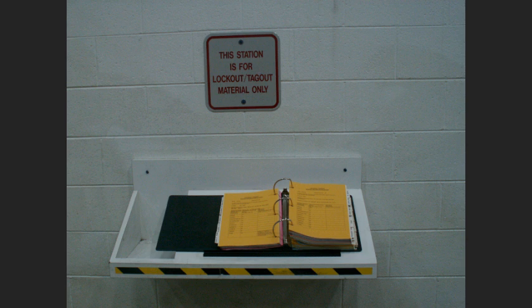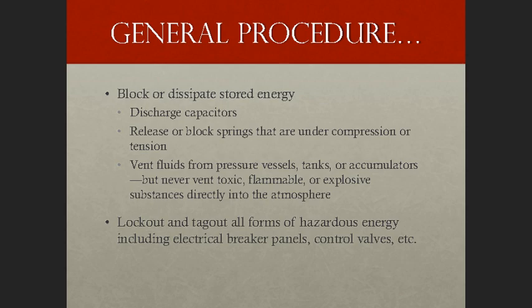Some companies require authorized Lockout Tagout employees to complete a log before beginning work, recording what equipment they're locking out, times, dates, and other logistical details — this is a very good work practice. The second step is to block or dissipate stored energy where applicable. This may include discharging capacitors, releasing or blocking springs under compression or tension, and venting fluids from pressure vessels, tanks, or accumulators — but never vent toxic, flammable, or explosive substances directly into the atmosphere.